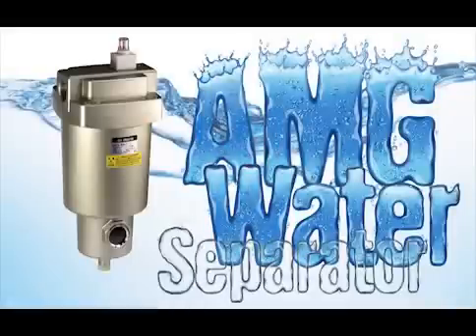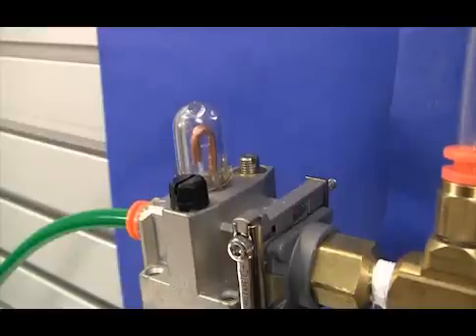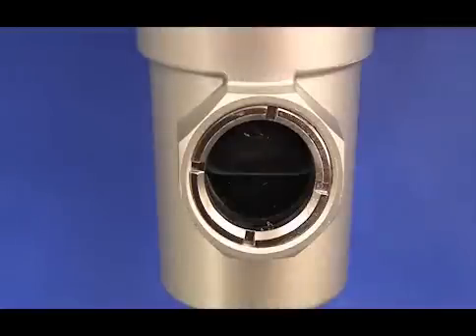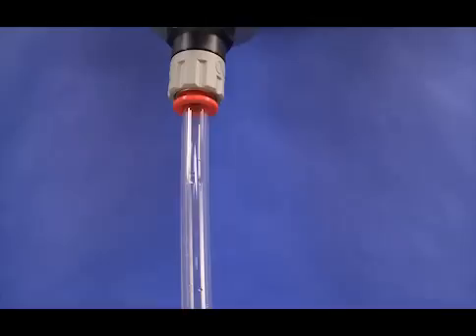Let's address this all-too-common situation by using an AMG water separator. Using the same water-contaminated air as our source, we'll route the air into an AMG water separator. The AMG unit uses a specialized filter to separate the water from the air and provides dry air as an output. Once the water reaches a predetermined level, it activates a float which drains the water out of the AMG unit.